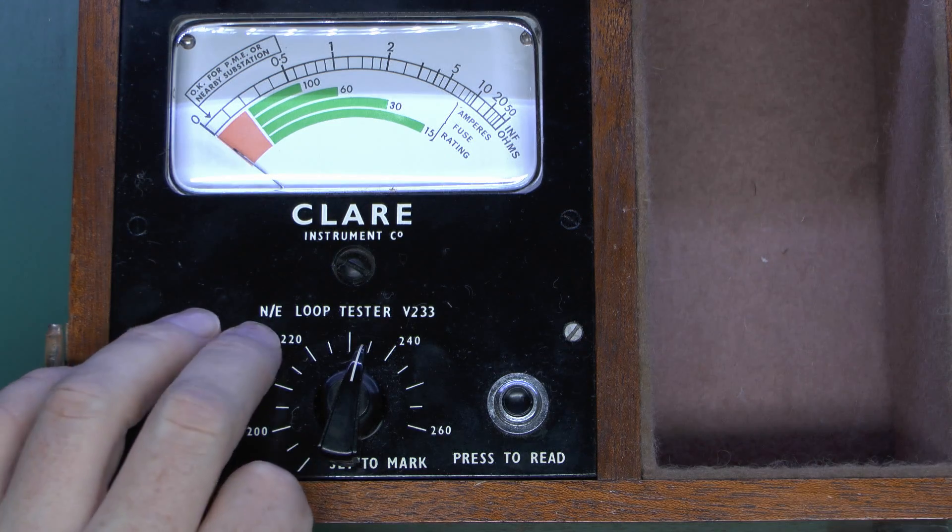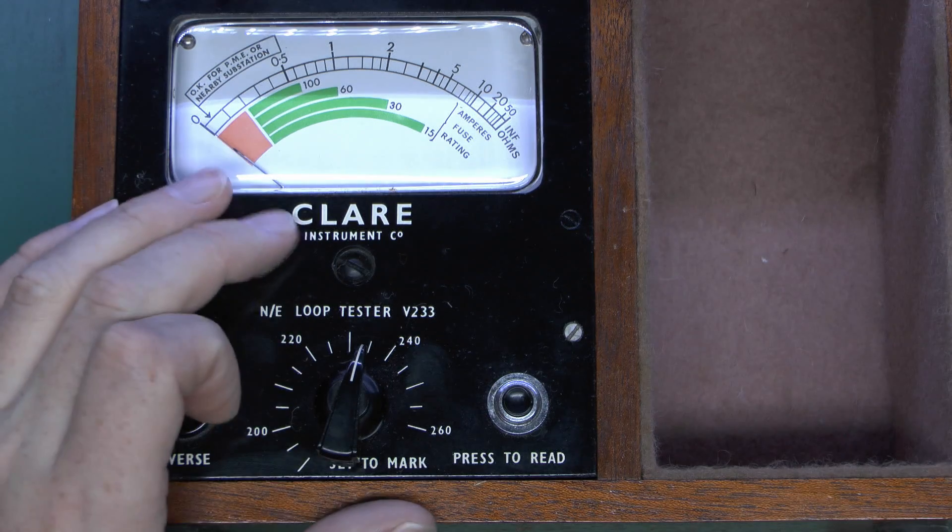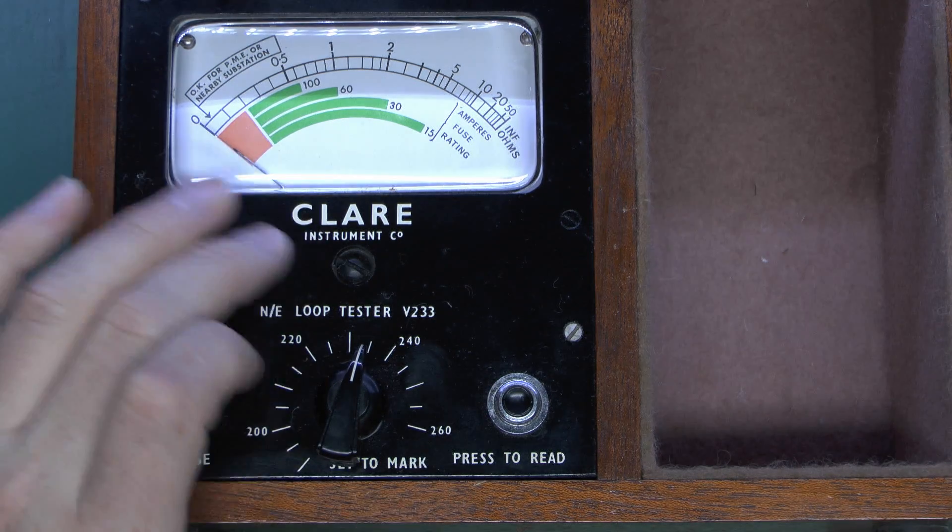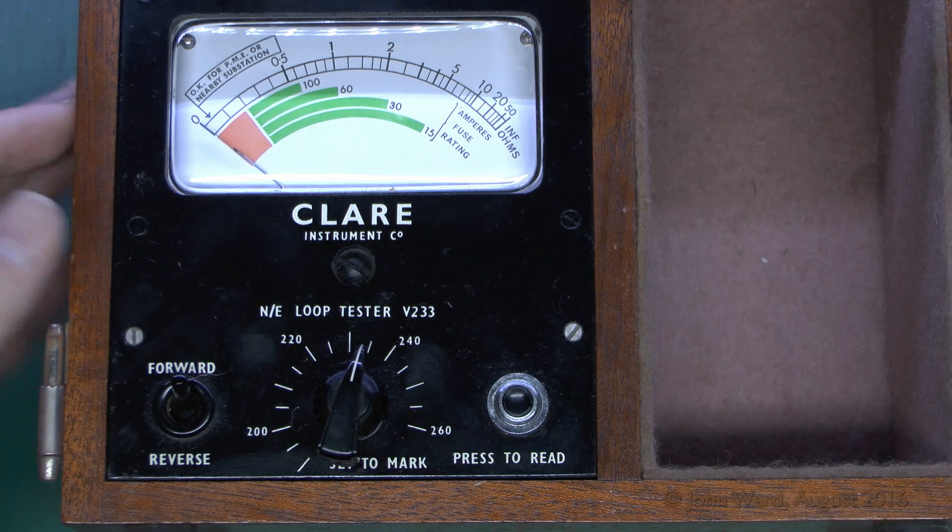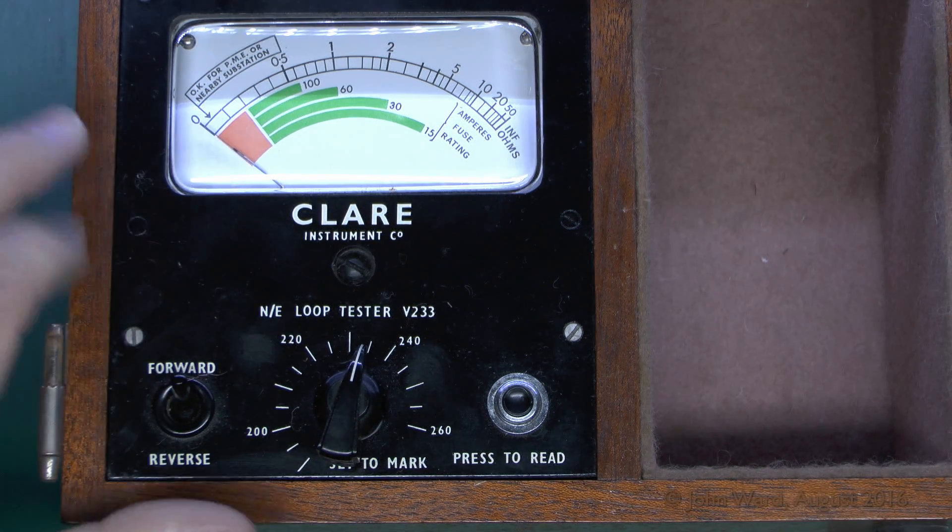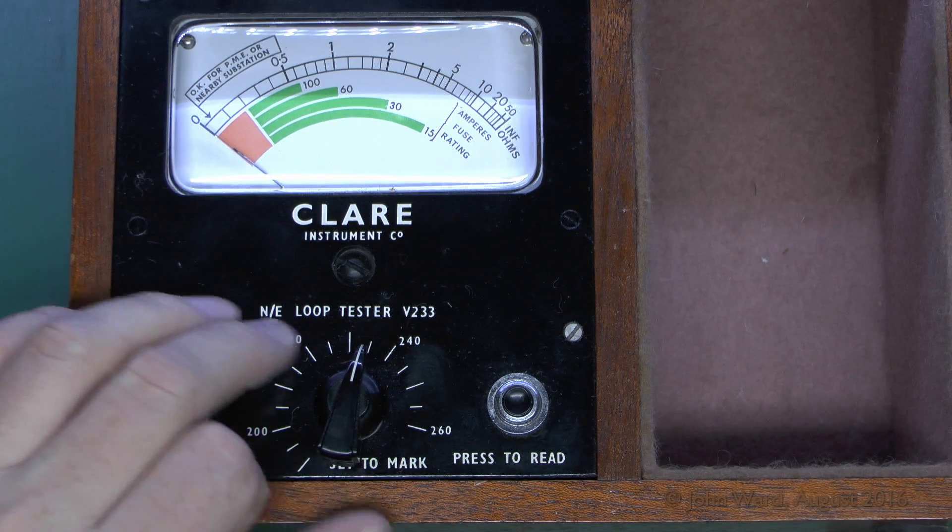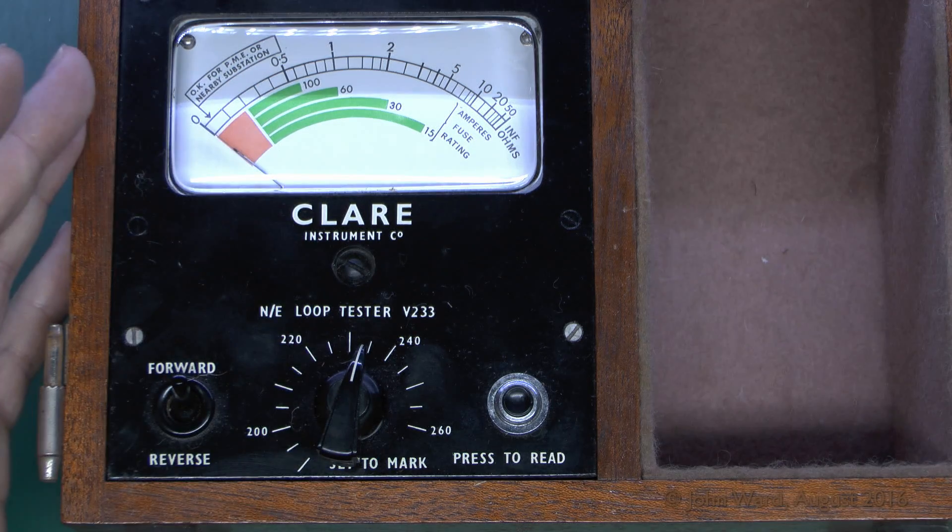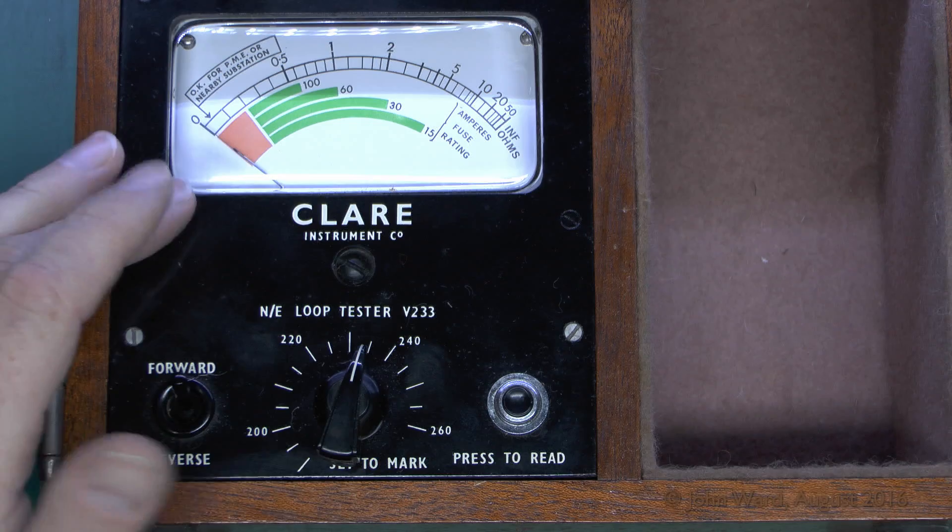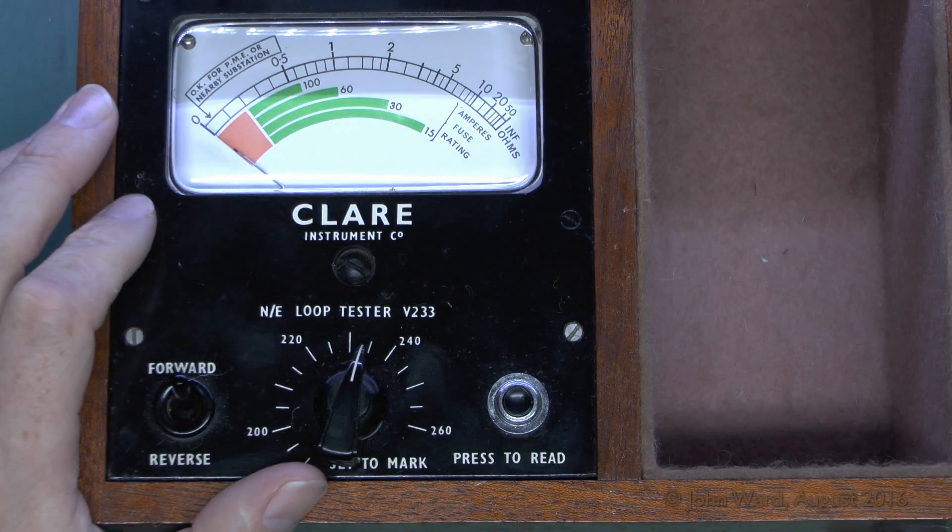So this is a neutral earth loop tester, model V233. Clare, as a company, doesn't exist anymore, but when they did they made a whole series of test equipment, all of which was primarily in this kind of wooden case style. This one's slightly unusual in it's a neutral earth loop tester, which is to test the impedance between neutral and earth. This is of the type that actually injects a current into the loop there, and then you get a reading on the scale here in ohms directly.